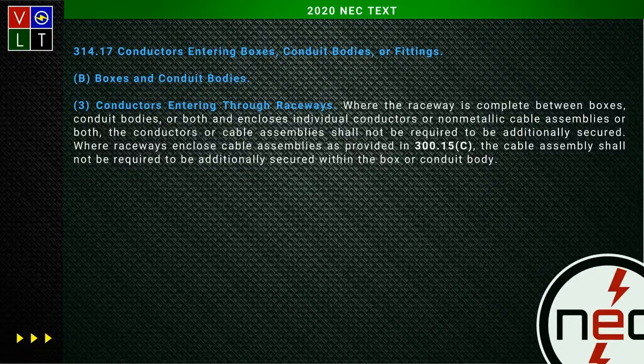So I want to point something out here. If you look, this talks about conductors entering through raceways, and it tells you where the raceway is complete between the boxes, conduit bodies, or both, and encloses the individual conductors. The other thing I want to point out is non-metallic cable assemblies, and then it says the conductors or cable assemblies shall not be required to be additionally secured. I want to point that out because I've heard people say you can't run non-metallic sheathed cable in raceways.